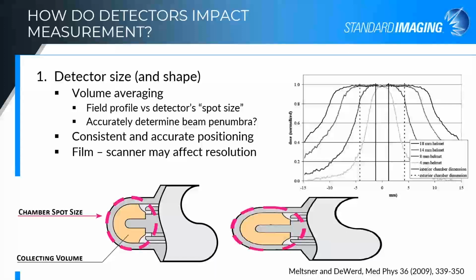And that can decrease the measured value in the center, because your film scanner doesn't recognize just how dark the film is at the center if it has that extra light scattering around. So just to be aware, as you get down to these really small fields, your film scanner may artificially flatten them just a little bit, due to some of the scatter within the film scanner itself. So having multiple detector types, having multiple different ways to measure your field profile, not just relying on one type of detector, is critical here as well.